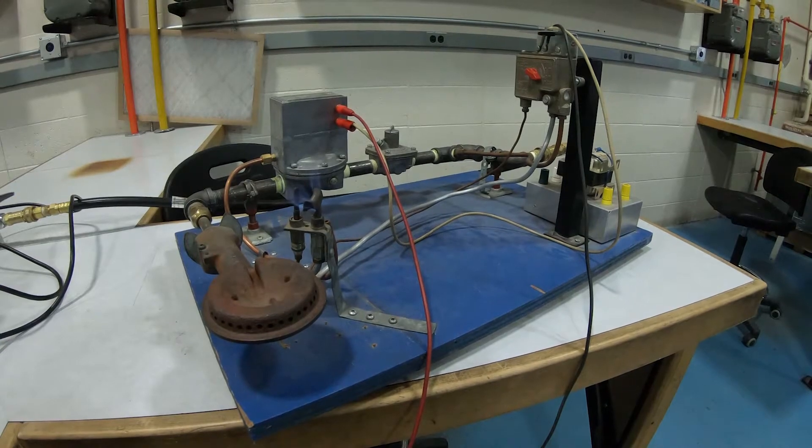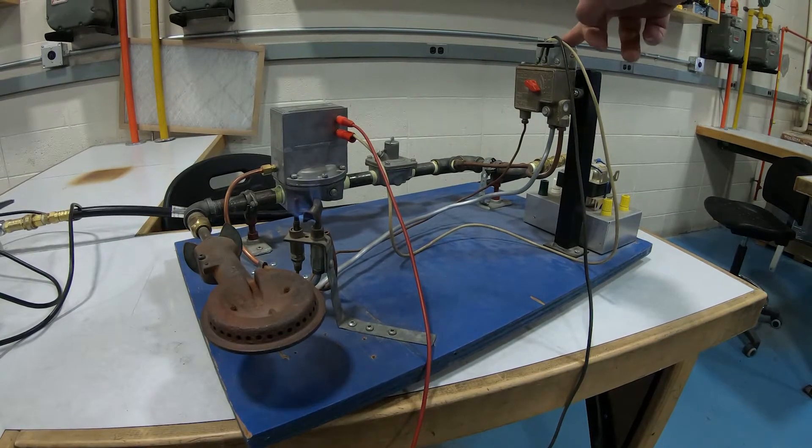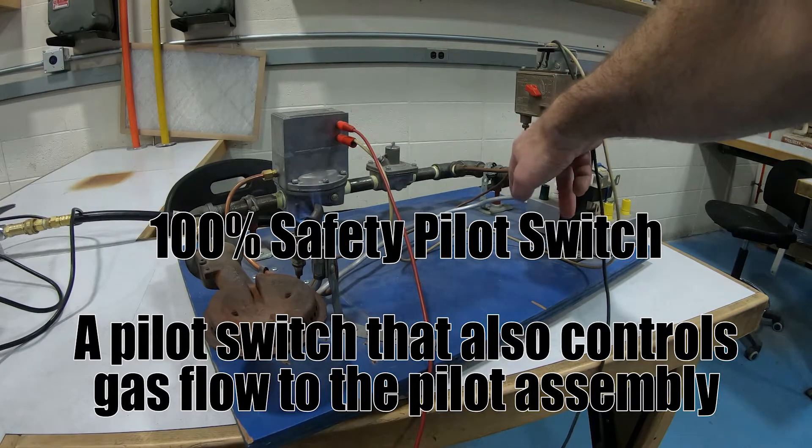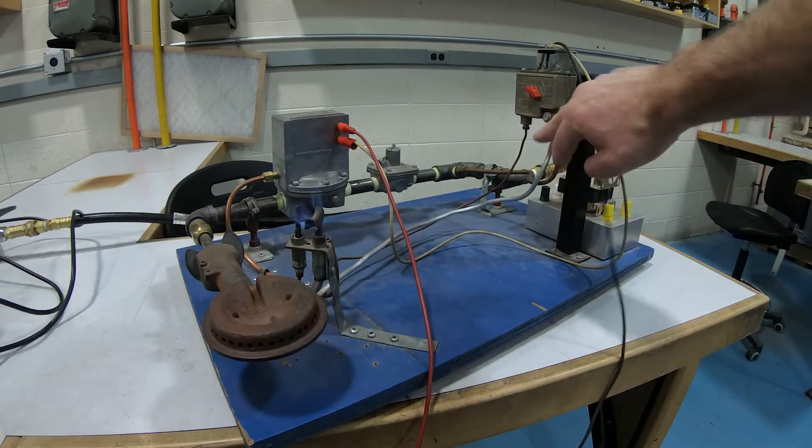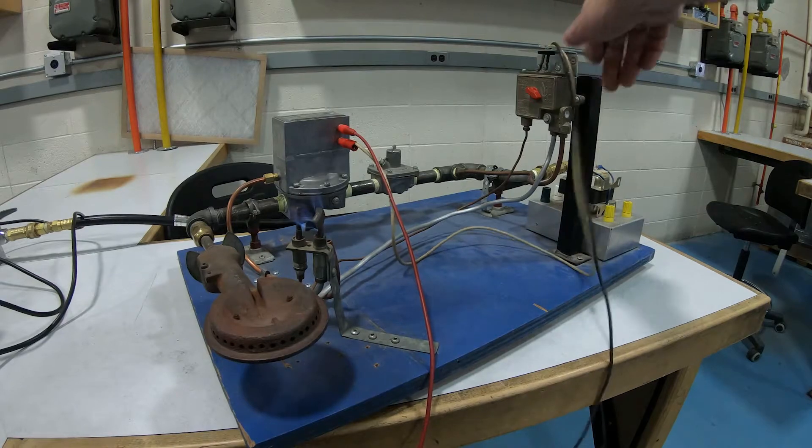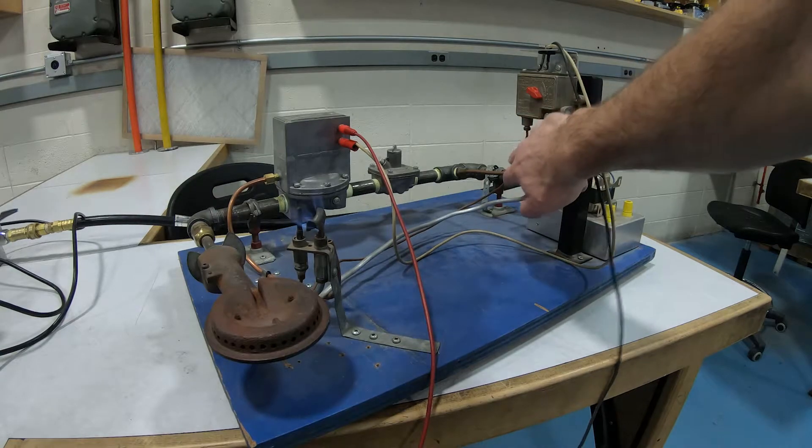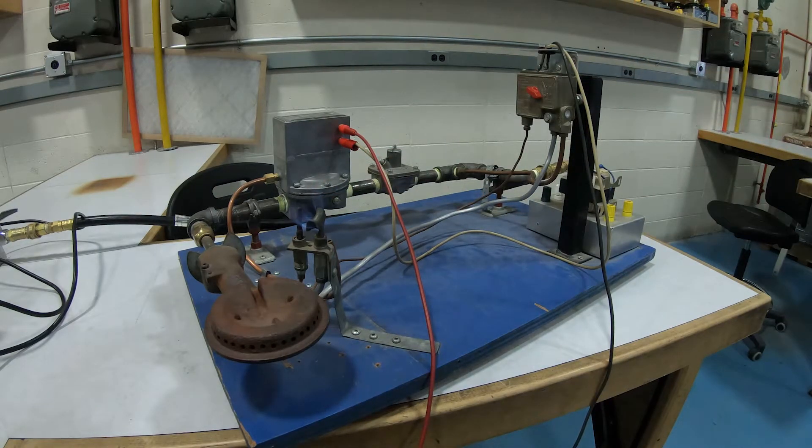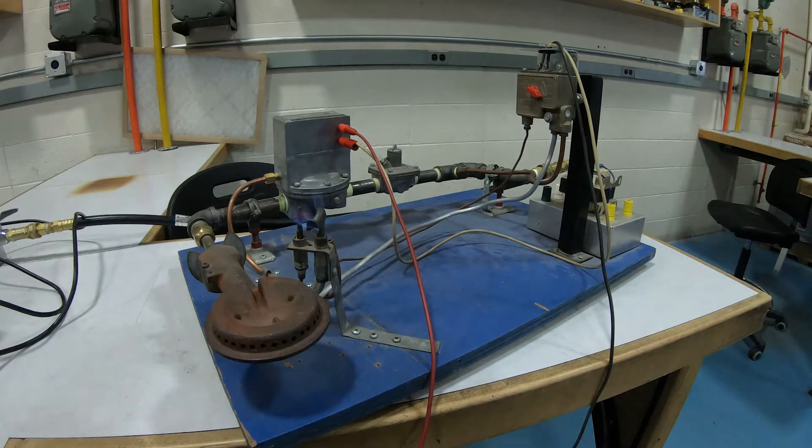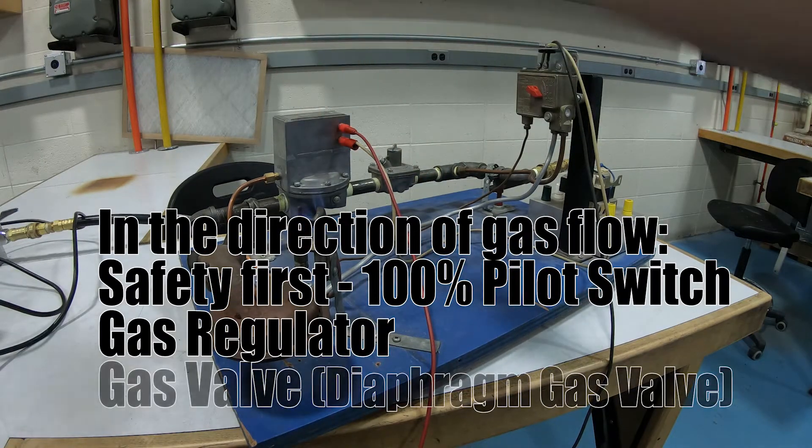Now, I have one more 100% safe setup to show you. Now, we've got a slightly different device right here. This is still a pilot switch, but it's a 100% safe pilot switch. Meaning the gas comes in through here. And the pilot gas then comes down through there. So not only is it an electrical switch, it also switches the gas as well. Once again, it just uses a regular thermocouple connected the regular way. And in this case, we're once again using a diaphragm gas valve. So once again, safety first, regulator, gas valve control.